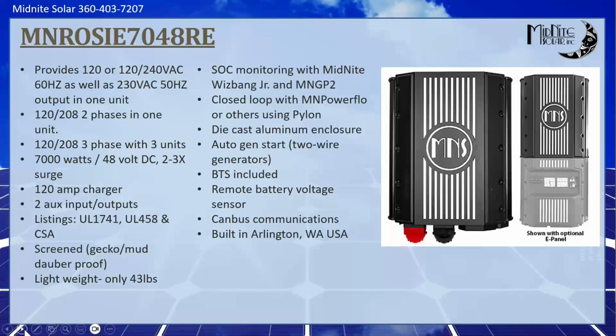On the Midnite Rosie architecture, the battery temperature sensor can still be used. And when you select lithium, it'll disable temperature comp, but it allows you to set low temperature stop charge. So instead of the BMS having to control you charging the battery, you can set the equipment to stop charging at, like, 30 degrees or 32 degrees or whatever temperature if you're not using a heated battery.